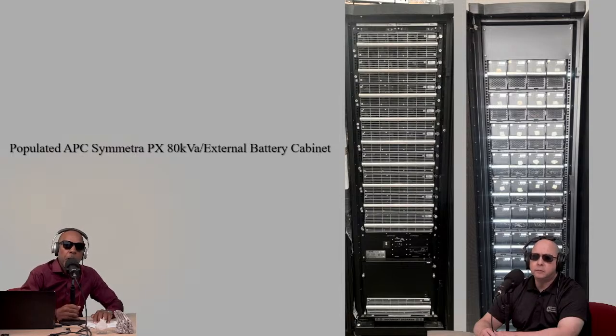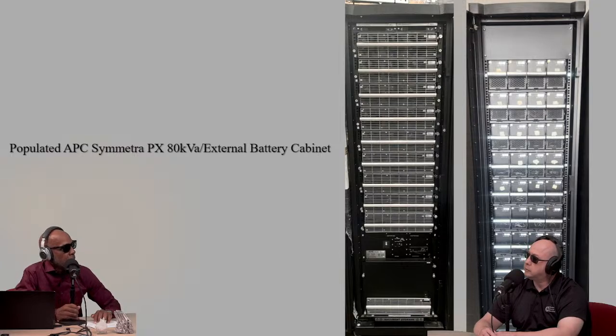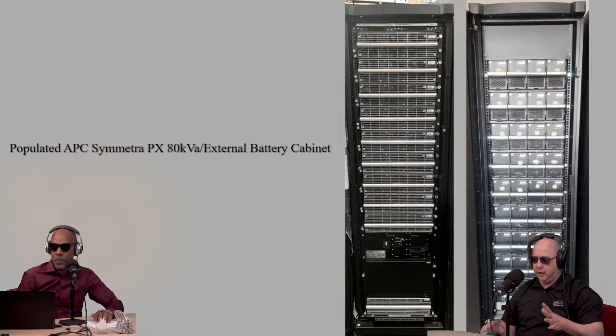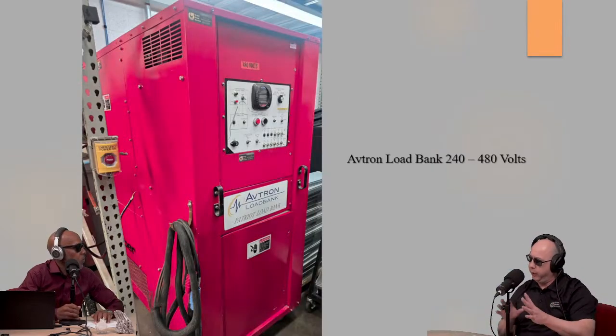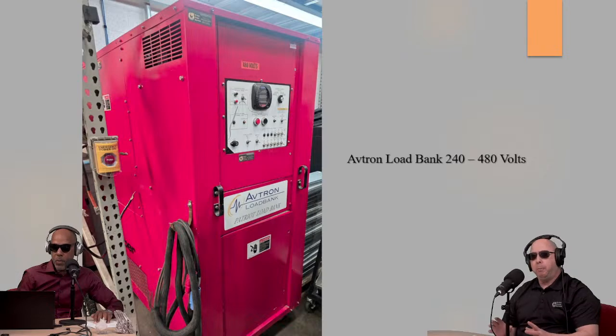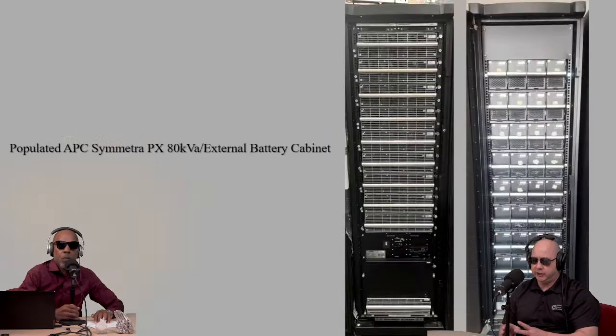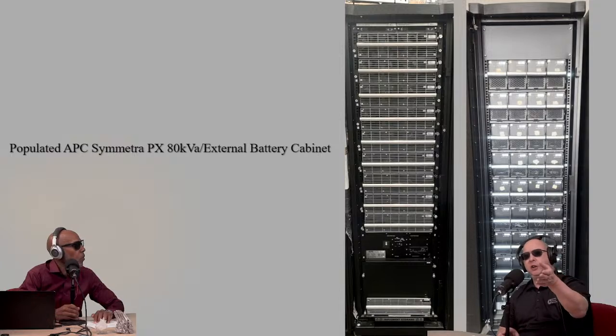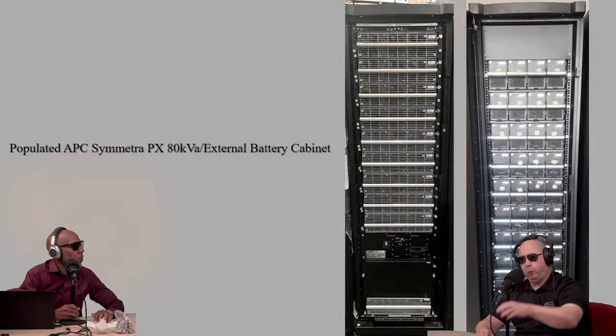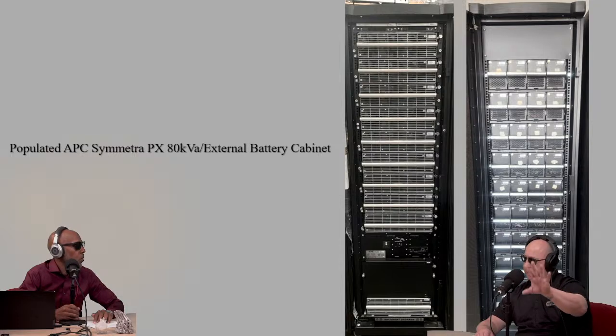Why do we want to test the unit fully populated? Well, even with an 80K unit, you can make it a 20, 30, 40, or however many modules you need. But the reason we test every slot fully populated like this is because if a customer only has 4 modules and one of their slots goes out, we want to make sure all the subsequent slots work. So if they have to move it to a different slot, they're not going to lose the use of that power module. We test it like this to make sure everything works, and once that's good, we set it up to what the customer ordered, then go from there for final QC reports.